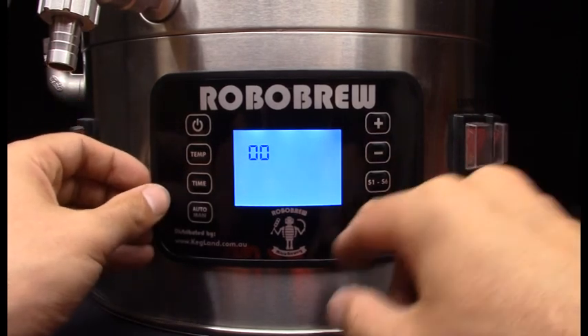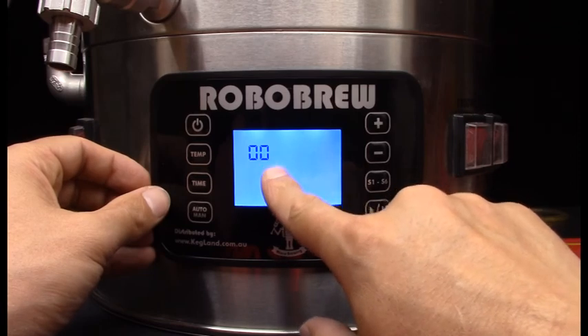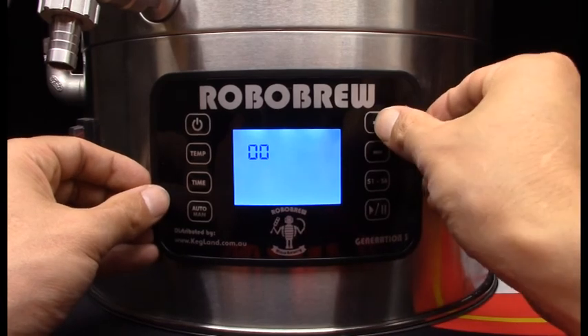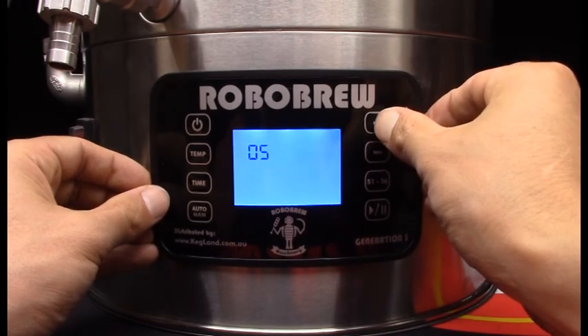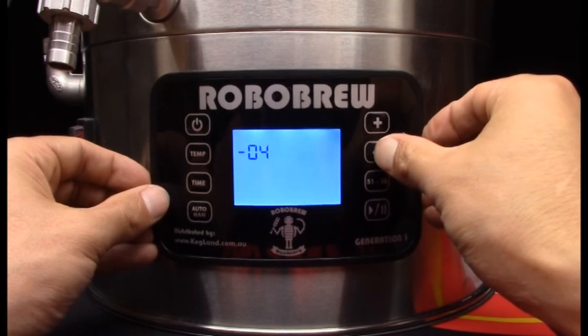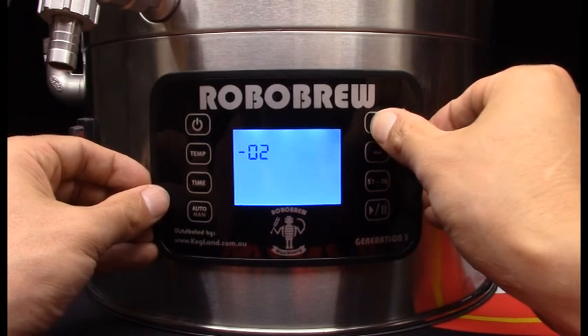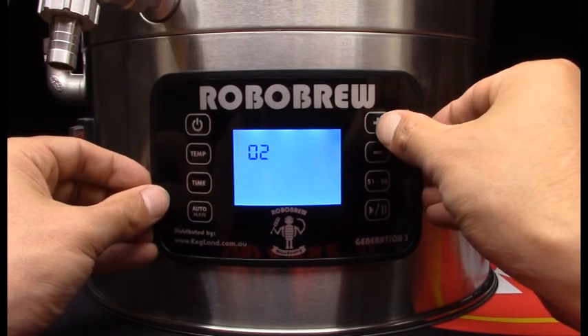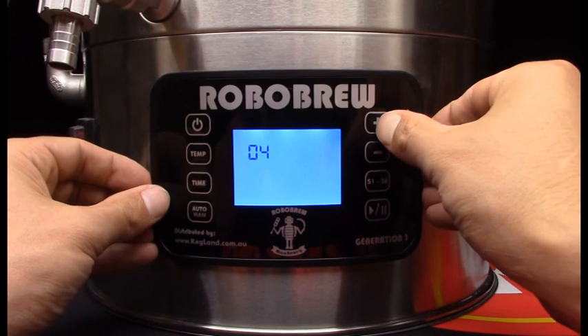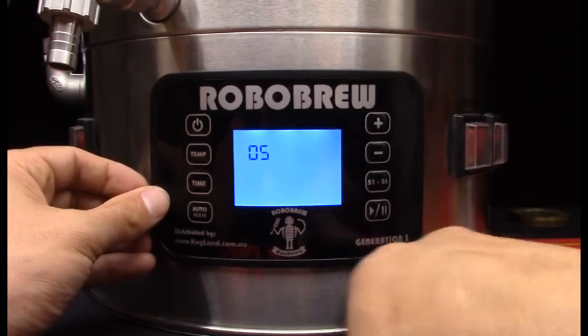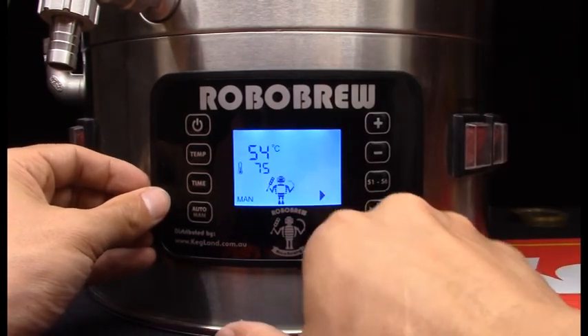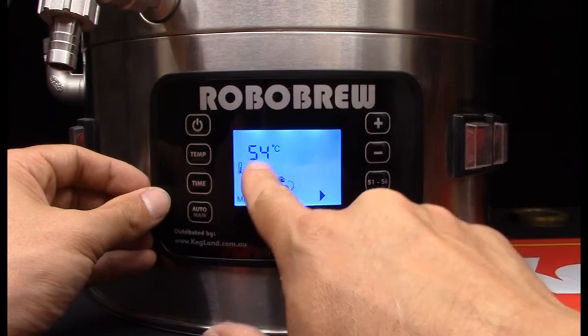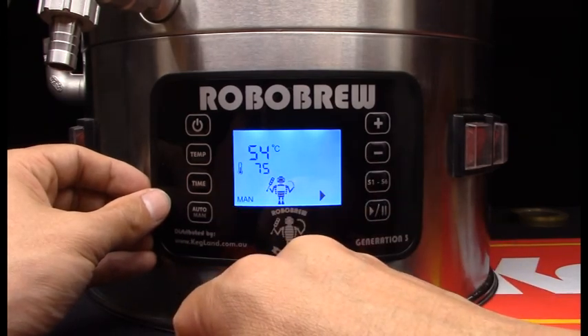There we go and then it goes into this calibration figure setting so I'm going to increase this to four. Now you can go all the way down to negative 10 actually to positive 10 but because I want to increase the display temperature by five degrees I'm just going to go like that then hit the play pause button it'll jump back to the home screen and as you can see it's jumped up by five degrees.